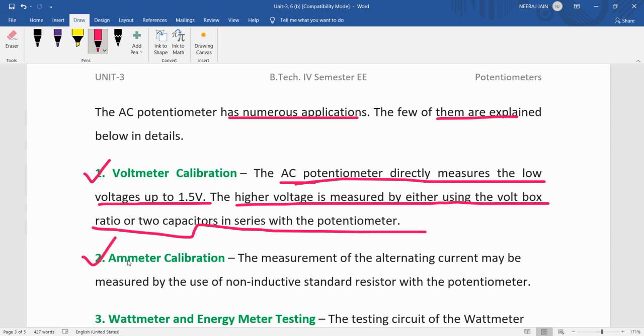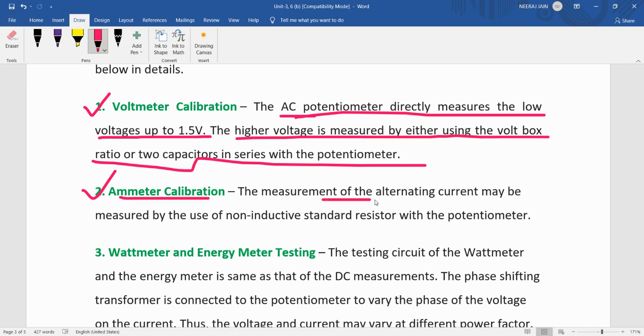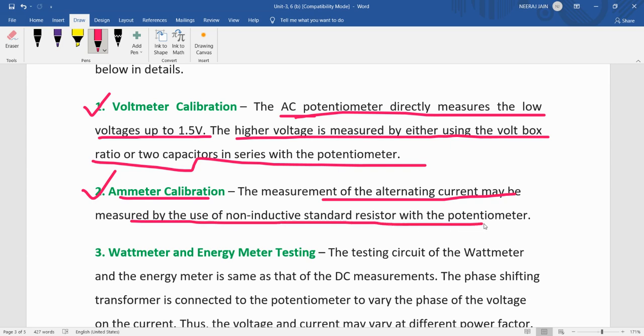The second application is ammeter calibration. The alternating current may be measured by the use of a non-inductive standard resistor with the potentiometer. We use a standard non-inductive resistor and compare the voltage it shows with what the ammeter is showing — that calibration can be done.